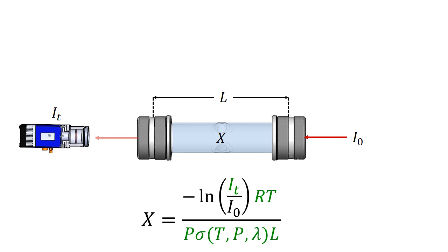And that's actually very easy. All you have to do is vacuum the gas sample cell down to where there is nothing in there and nothing to absorb the signal. And at that point, now the transmitted intensity is the initial intensity. The other value of this is that A, you have the same signal set from the same detector, so the conversion is automatically the same. Also, any kind of absorption or reflection of that laser signal that might have happened at the windows or laser alignment or anything else is automatically accounted for here. So this eliminates a lot of sources of potential signal change that aren't actually due to a change in the sample concentration.